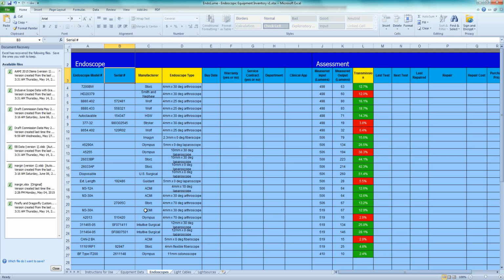So, the best thing for the hospital to do is to test or baseline all their scopes, light cables, and light sources. The best would be if they baselined them when they were new. On the first tab, under the equipment tab, they would put in all that data and could set their guideline. They could run a test and set their guidelines there. Then over time, for that particular cable, scope, or light source, based on a serial number, they could watch the degrading of the device over time. They could see that eventually it goes down and hits the red area, and they know it's time to change it or get it repaired.